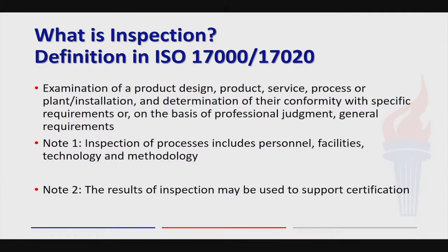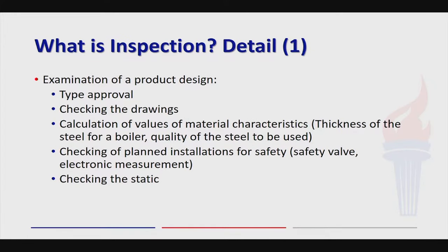Inspection involves examination of product design and service. The results may support certification. When looking at inspection of pressure vessels, we're looking at what type of weldment, what type of x-ray has to be performed, whether it's been done by a certified body, whether the process was done in the proper sequence, material characteristics — was the proper steel used, was it heat treated properly? We're also looking at planned installations.